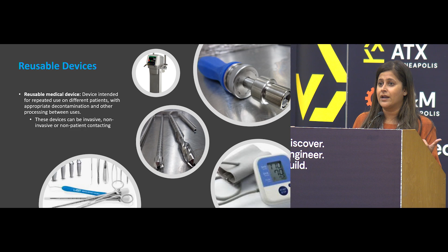Now, when I talk about reusable, a lot of people assume these are devices that are used on patient. Yes, these are devices that are used on patient, and they are used repeatedly. So if it's used on one person, it gets cleaned, disinfected, and sterilized and used on a second patient. And this happens until the device breaks down. Now, you might say, when does this device break down? Is there something that we know or we have to test for? Recently, there hasn't been anything, but I will go on and you will see in my slides when we're starting to look into stress testing and repeated use of these devices, and when is the break point of the materials that will cause a safety problem when being used.